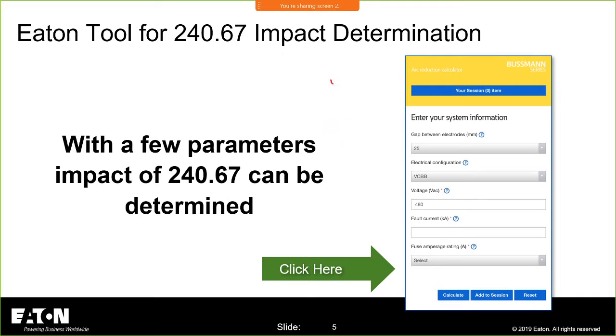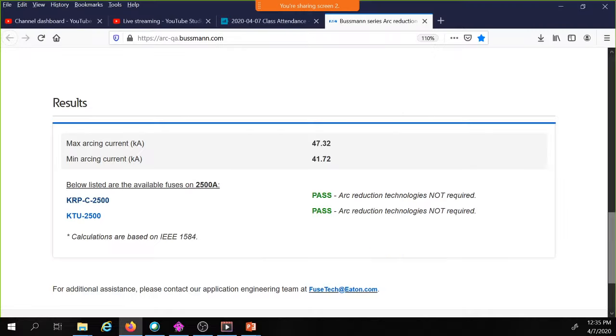Now, the reason we bring all of this up is because you have to understand that the code is going to require you to compare in the worst case scenario when you're thinking about moving into either an instantaneous region on a circuit breaker or a 0.07 second clearing time. The lower of these fault currents is going to be your worst case. It doesn't say this in the code, but this is Tom's advice. From a power engineering perspective, we know that lower arcing current can give me a longer clearing time. So I want to make sure that the lower arcing current is either in my zone selective interlocking region, in the instantaneous region, or at a clearing time of 0.07 seconds or faster. So everything I talk about moving forward, with regard to 240.67 and 240.87, I'm going to be keying off of that lower arcing current.